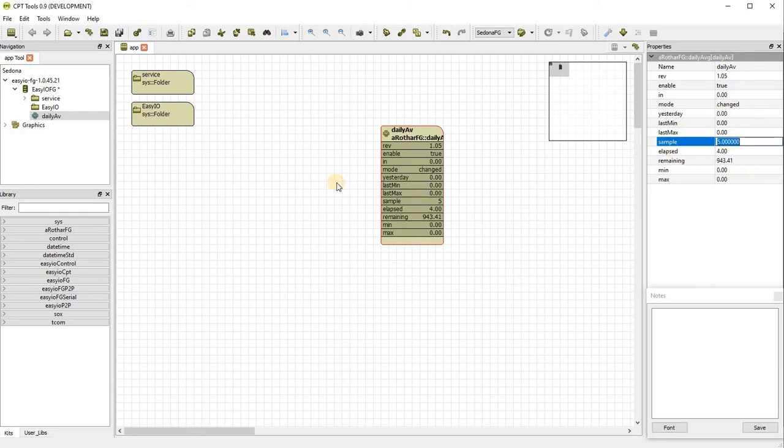You can change the sample rate based on polling. So if you're using Modbus or BACnet and you've got your polling set up at 15 seconds, there's no point sampling every 5 seconds, because obviously you will load your samples. You might as well marry those two things up so that it's sampling correctly. It will sample 0. So if you've got nothing plugged in, it can sample 0. But if you set this to null, that will be disregarded in the calculation.